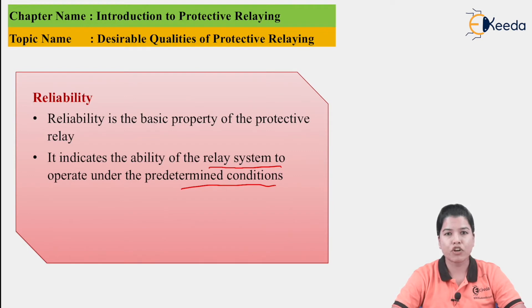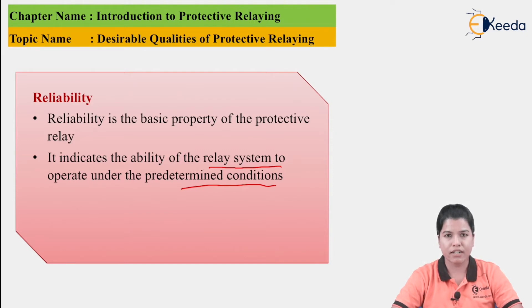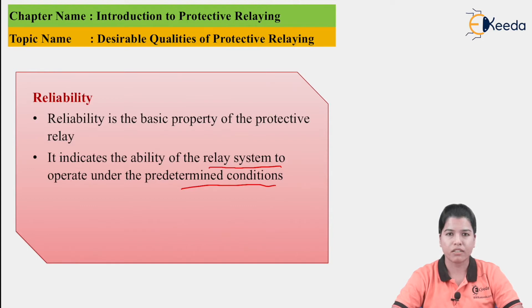The predetermined conditions are certain values of parameters such as voltage and current that are already fed into the relay. For example, if the value of current set in the relay is 5A, then up to 5A is the normal condition. But if the current goes beyond 5A, then the protective relay should operate. This is the predetermined condition already fed to the relay.